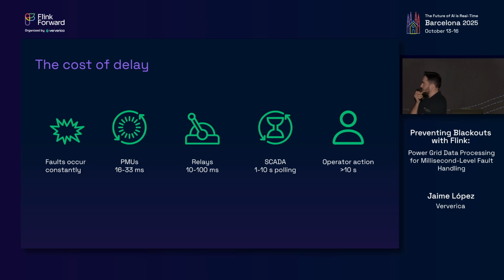So you get a fault that occurs suddenly. Your PMU is going to know about it in about 20 milliseconds, because the voltage is going to be high or low, the frequency is going to be high or low. The relay that controls that generation unit can also know it in less than 100 milliseconds, and will often do something. Will often trip, disconnect from the grid, activate a protection, etc.